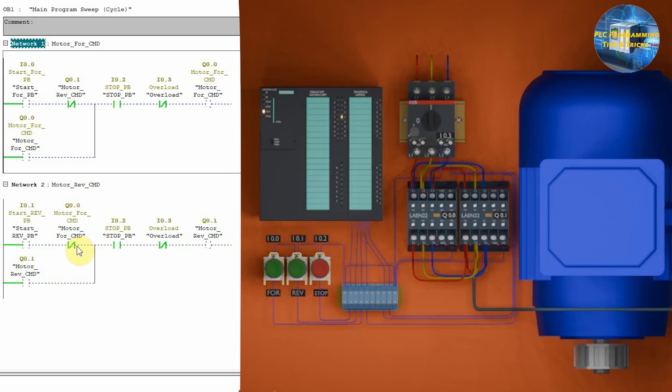So, this means that we can only turn on the motor reverse command Q0.1 when the motor forward command Q0.0 is off. If we press the motor reverse start push button I0.1 and the motor forward command Q0.0 is off, this will turn on the motor reverse command Q0.1.